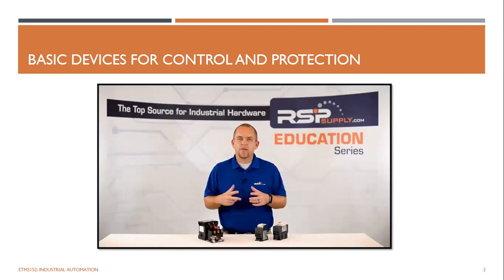Lastly, commonly used with motor starters are motor circuit protectors. These are essentially circuit breakers that are specifically designed to be used with motor starters. They operate by preventing large spikes in current that might be caused from a short circuit. Motor circuit protectors use a form of magnetic protection, which is specifically designed for these types of spikes in voltage. For more information on magnetic protection, please see our circuit breaker video that talks about this. We will link it in the description below.